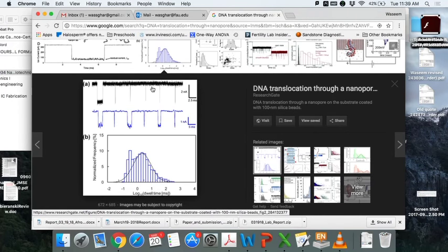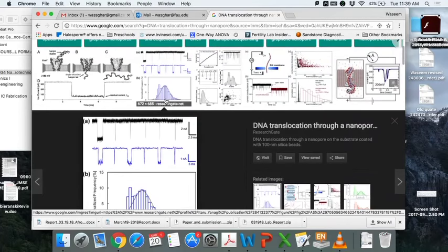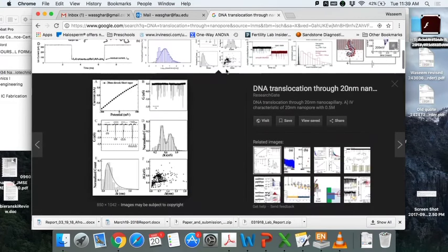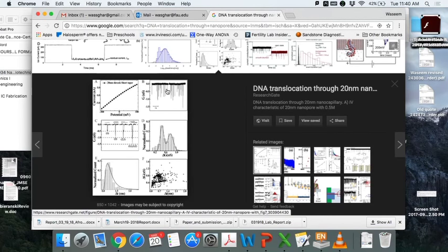But sometimes you get a very bad signal. So it's very difficult to differentiate. For example, this is also nice, but sometimes it's difficult to really see whether it's a signal or noise itself. The equipment has to be super stable, on a vibration-isolation table to record these readings, and then you also have to put the whole thing in a Faraday cage. A Faraday cage is just a metallic box where optical light and other radiations will not affect your experiment, and I've seen that happening.